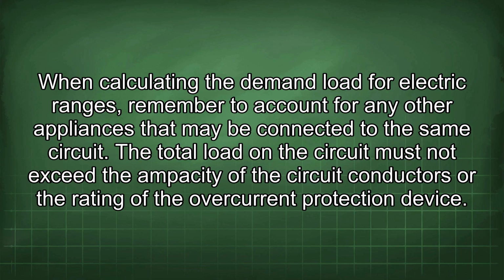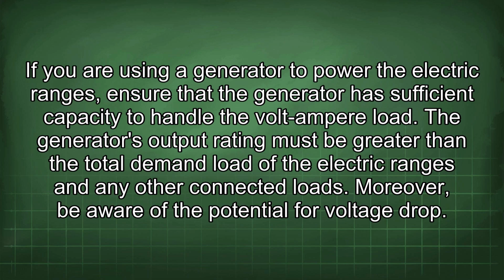The total load on the circuit must not exceed the ampacity of the circuit conductors or the rating of the overcurrent protection device. If you are using a generator to power the electric ranges, ensure that the generator has sufficient capacity to handle the volt-ampere load. The generator's output rating must be greater than the total demand load of the electric ranges and any other connected loads. Moreover, be aware of the potential for voltage drop.